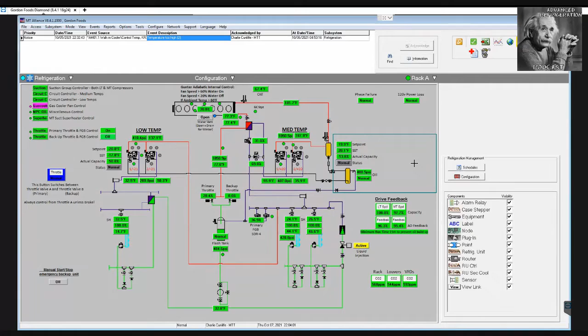Kevin, you've probably looked at a bunch of the graphs for these. You've always said the 326 controller has a decent program in it, but normally, if you get it right off the shelf, you're looking at like a 40 or 50 pound differential between the flash tank and basically the high and low set point. What have you seen when it's being controlled through Micro Thermo?